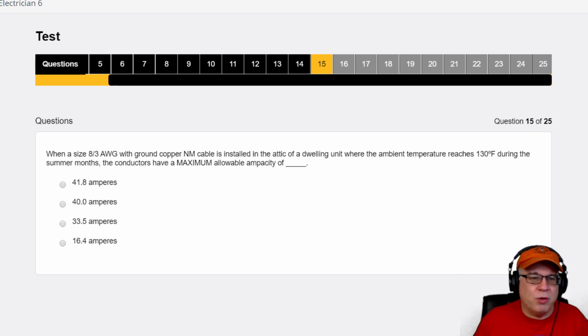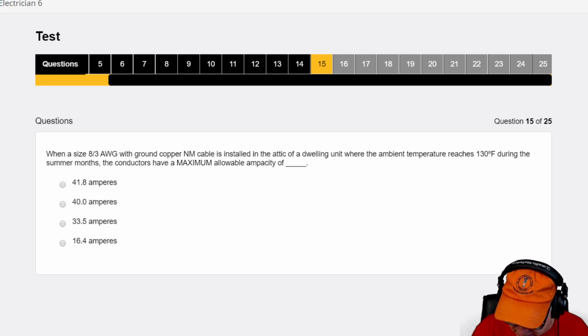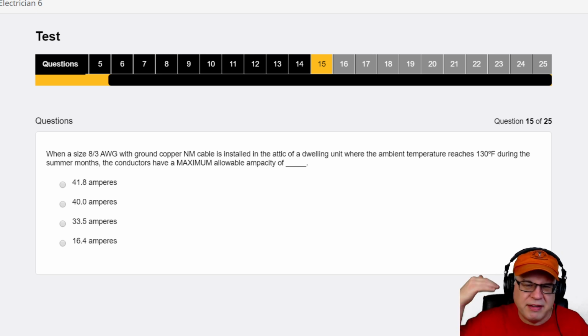So the first thing I want to know is what the ampacity is of an 8/3 NM, right? And did it say it's in insulation? No, it's just an ambient temperature. It's not in insulation or anything. It's in an attic. We're just talking heat. The only thing we're doing is heat.